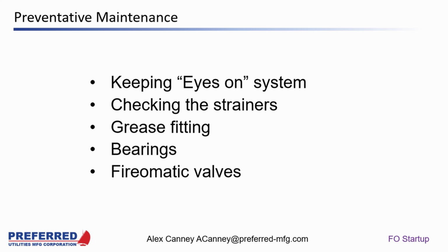A good rule of thumb for most preventative maintenance is to, like you said, visualize the system on a periodic basis. It doesn't really have to be daily, because most of these systems are going to sit until they either do a test or there's a true emergency. So on an annual, semi-annual or quarterly basis, the customer needs to take a look at specific things, making sure there's power to the panel and that everything seems to be reading correctly. Taking a look at the strainers, whether the system has a simplex strainer or a duplex strainer. You need to open that up periodically to verify that there's no debris in there, because a lot of times if it's a new installation, you could have slag from construction or welding that could get clogged up, or you could have something that is trashing the system, maybe a bad delivery of oil. That's the whole purpose of those strainers, to keep that stuff out of this pure fuel that the generators need. They don't like dirty fuel whatsoever.